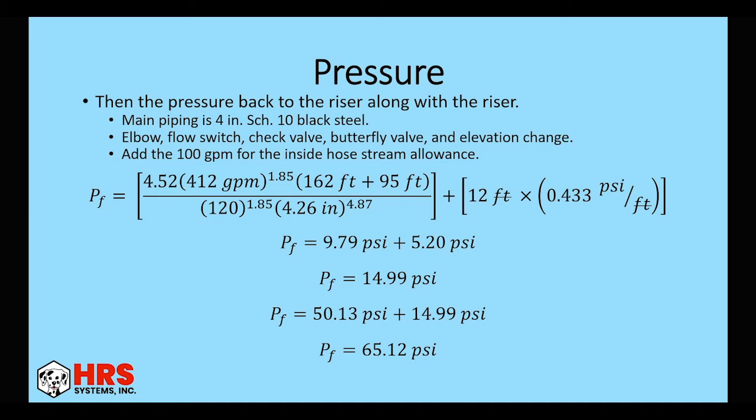Then we're going to take that, calculate it back to the bottom of the riser. So we have 412 because we included the inside hose. Our main we're going to say is 4-inch schedule 10 black steel. We also have an elbow, flow switch, check valve, butterfly valve, and elevation change all included in this one. So it's 412 times the 162. So that's the length of the main all the way back to the riser location. Plus the fittings and the change for elevation. We're at 12 feet, by the way. And then the internal diameter, 4.26. Then we add in the loss for elevation change. So our friction loss would be 9.79. Then our elevation change would be 5.2. So 14.9. So when we add that to our previous friction loss of 50.13 for a total of 65.12 at this point.